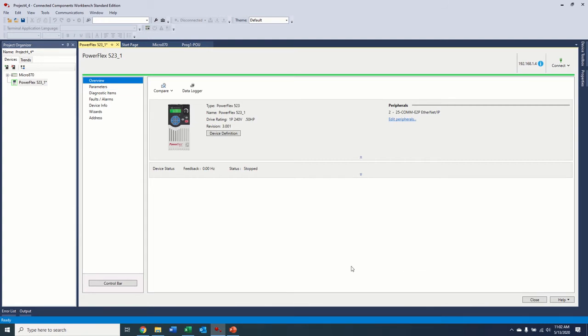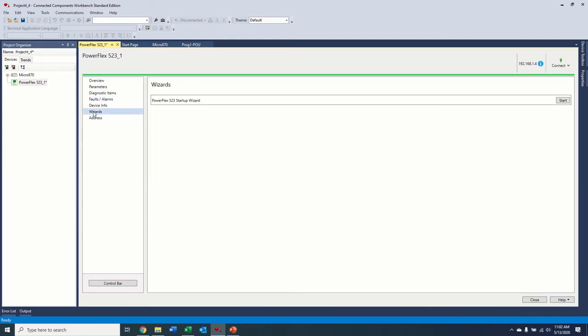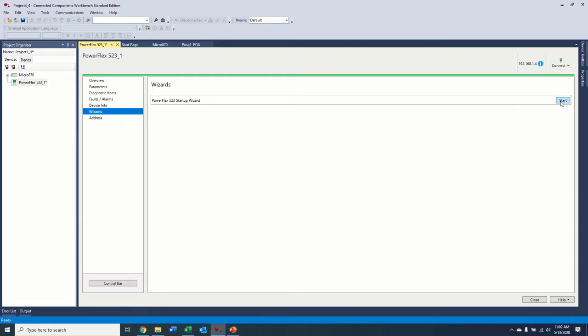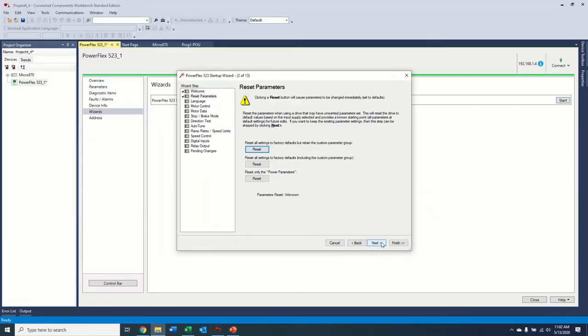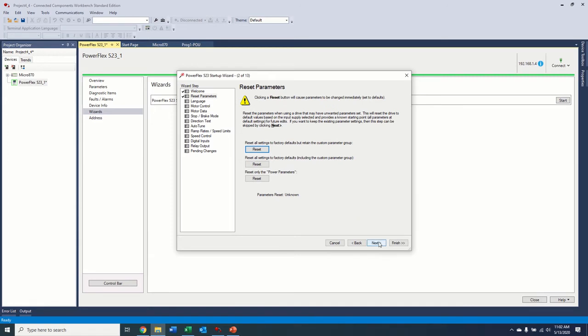Okay. So to step through our wizard, we're just going to click on wizards down here. And this startup wizard, you can do this offline if you don't have the physical drive. You can even do it with the 520 series, if you just have the control module off the front of the drive, you can also do that using the transfer utility. But we have a whole other video about that. But since we have the drive here, and I'm able to connect to it, I'm just going to stay connected and walk through the wizard. So we're going to click start. And it's just going to step us through all the stuff we would normally do. So if we want to reset the parameters back to default, we could do that. I don't want to do that because I don't want to lose the motor information of the motor that's in my demo box here. So I'm just going to leave them alone for now.